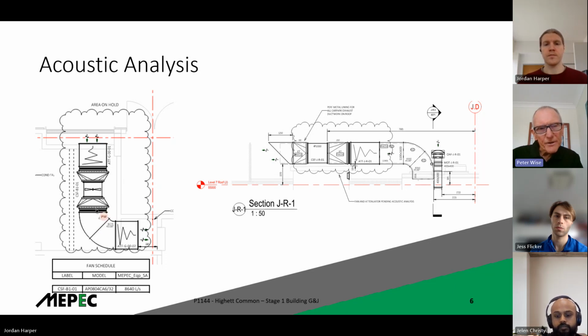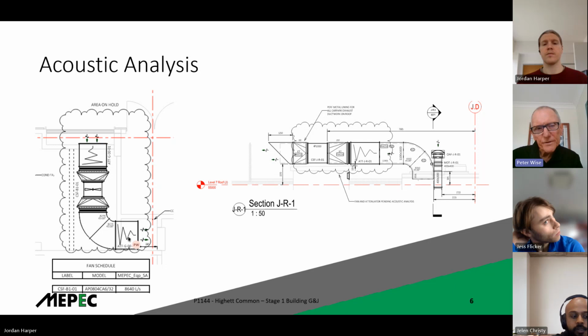Likewise, on the outlet side, you've got a very short transition, which is obviously a very tight space, but then you've got a bend before the attenuator. That's a no-no as well, because the air coming around the bend tends to go to the outside of the bend and not the inside, so you're starving the attenuator of air again.